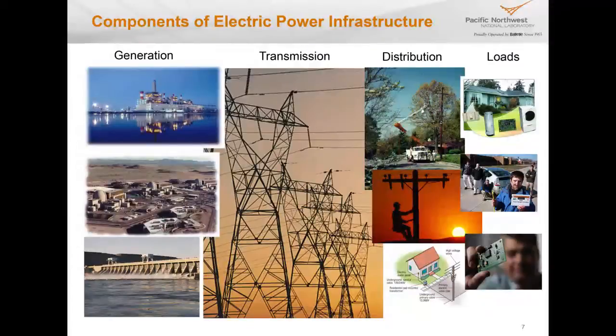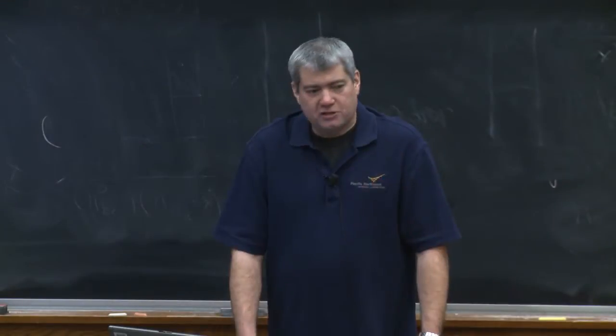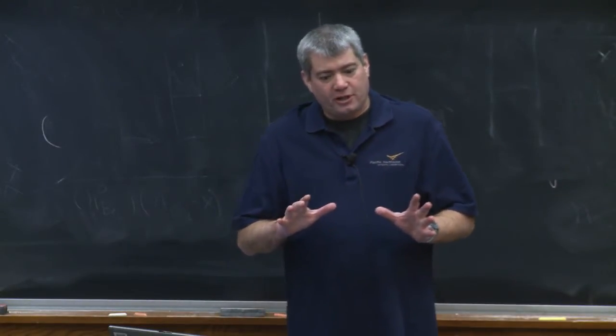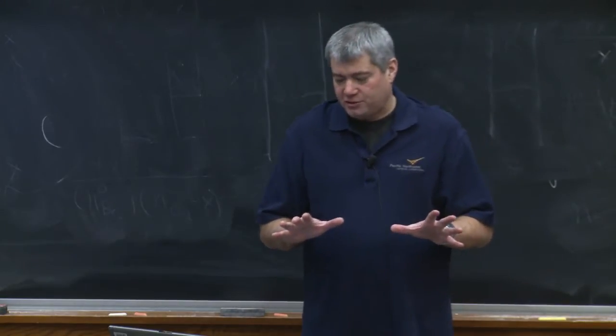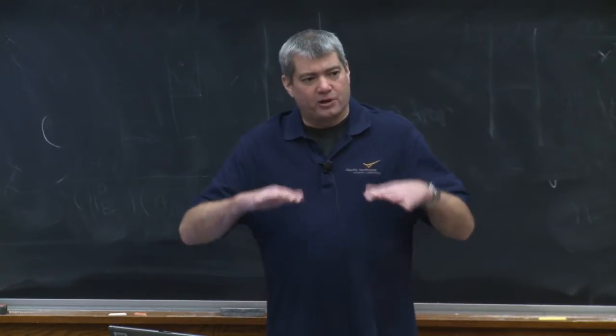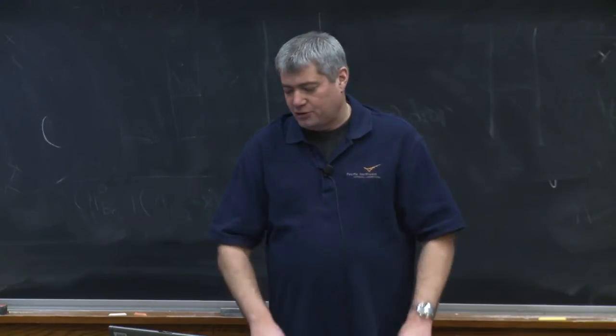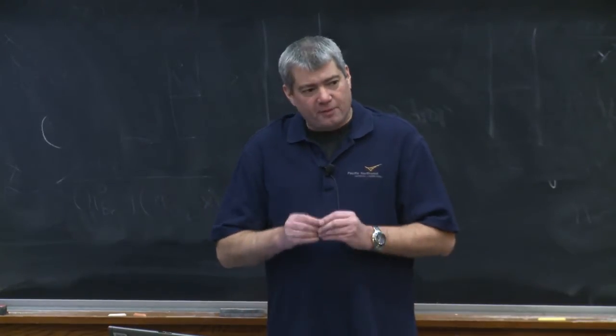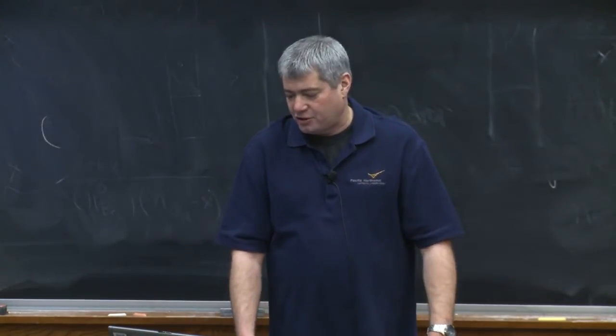The generation is brought from where it's generated to where it's consumed through transmission. Now the terms transmission and distribution might sound interchangeable to a layperson, but they're not in our industry. Transmission refers to the high voltage system that interconnects the substations - the mesh networked multi-state high voltage system. Distribution is from the substation to the customer, generally at a lower voltage.